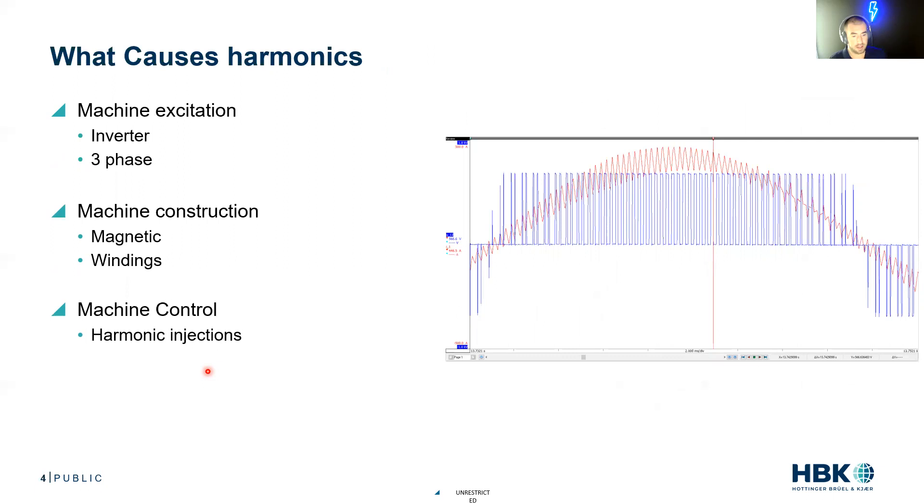So what causes harmonics? The machine excitation - this could be the standard three phase excitation or the inverter excitation. I love this example here. This is PWM voltage in blue and PWM current in red. We can see that our PWM coming out of that inverter has these little square waves. And what do we remember about square waves? That they cause all kinds of harmonics.